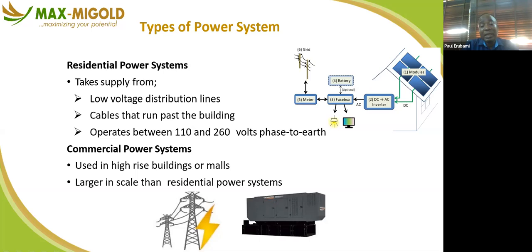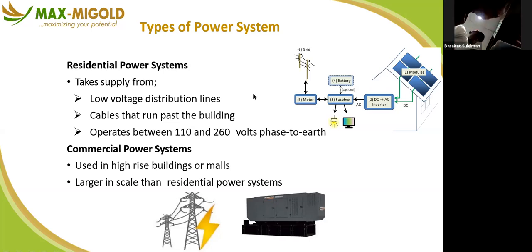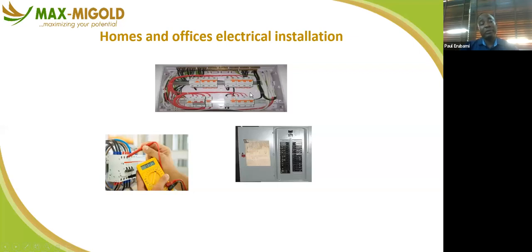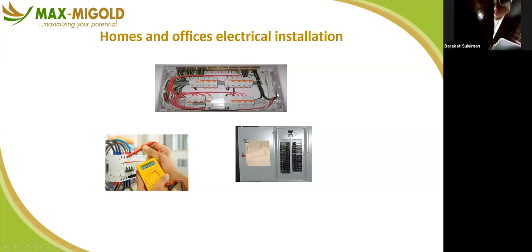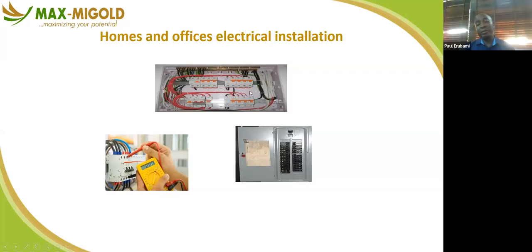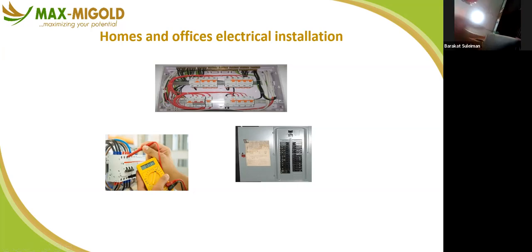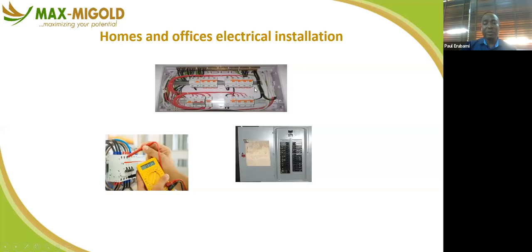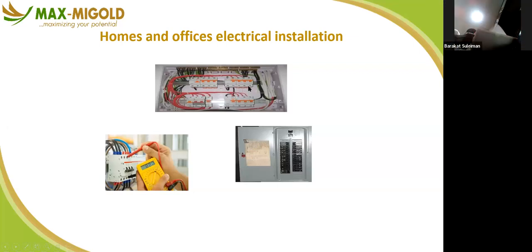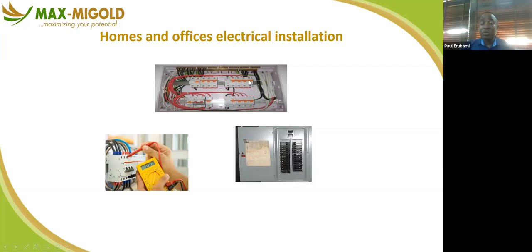So we have homes and office electrical installation. Like I told you when I mentioned the circuit breaker, before we used to use fuse to distribute our load, but now we are using circuit breakers of different ratings, and it makes work easy for everybody. You may not need to be an electrical personnel or engineer to know where the problem is. If you understand your layout, like this circuit breaker distribution board, the breakers are arranged by rating. We have 5 amps, 30 amps, 50 amps, 20 amps, 32 amps, 3 amps, as the case may be, depending on what you want to power. Like most ACs, you see a 20 amp breaker, and your sockets are tied to 30 amps or 50 amps. Your cooker is tied to a 30 amp breaker.